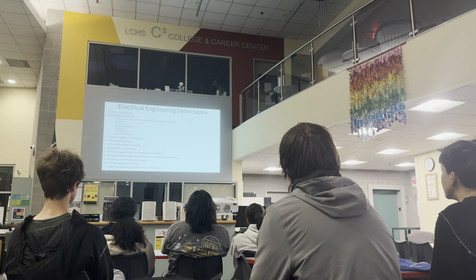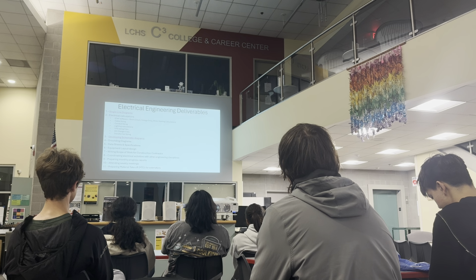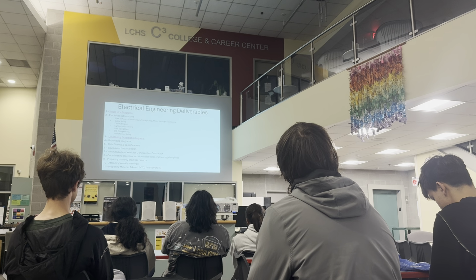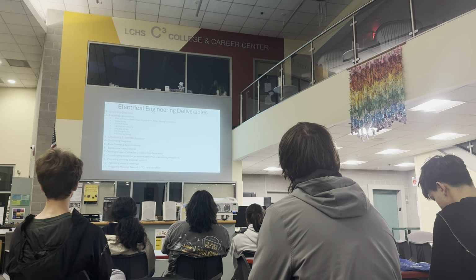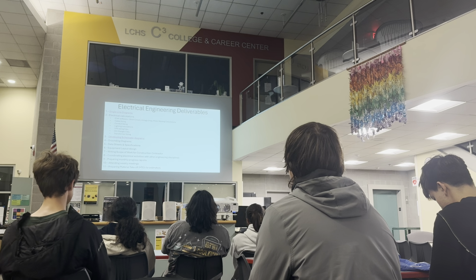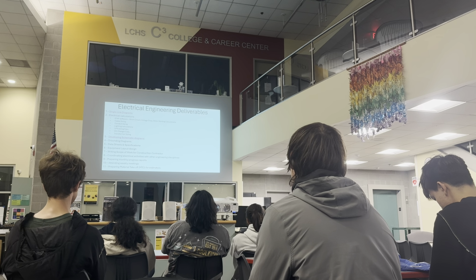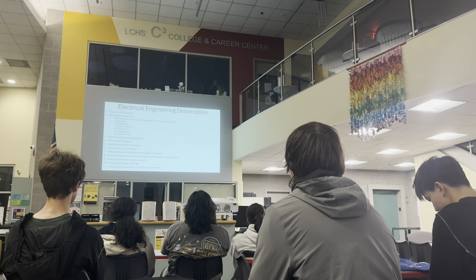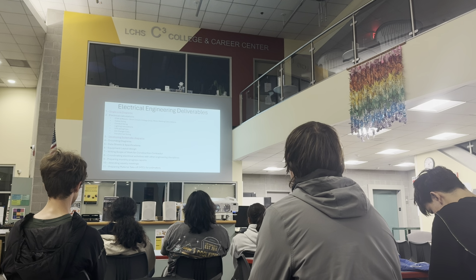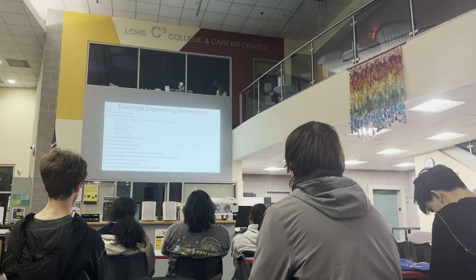Grounding diagrams, you have grounding diagrams, you have data sheets and specs. You have to develop data sheets: what kind of transformer, what size, what MVA, or motors, what kind of motors, UPS, uninterruptible power supply. You have to do equipment layout, how many pieces of equipment you have, what size they are, so you can size the buildings, the switchgear building, where does equipment go? You have to size all those, and you give it to architectural, and then they design the building. But you have to tell them what size it is, and where the equipment is located.